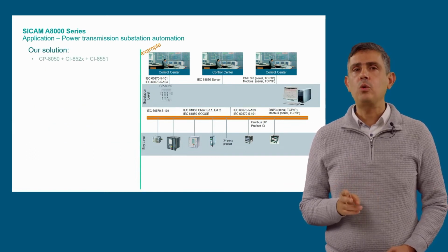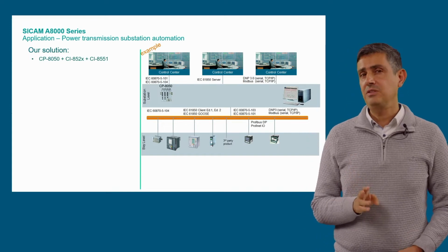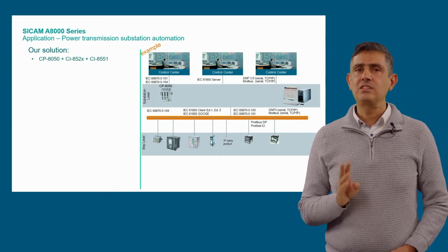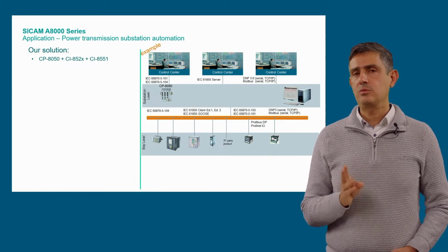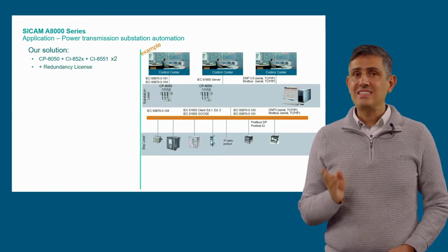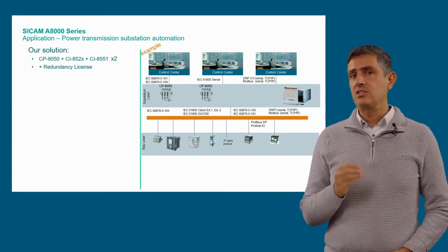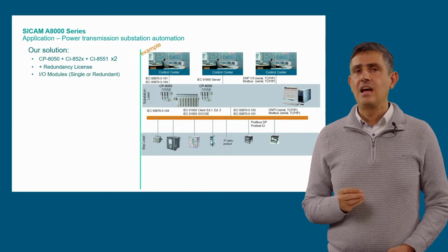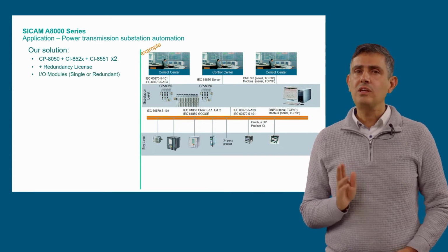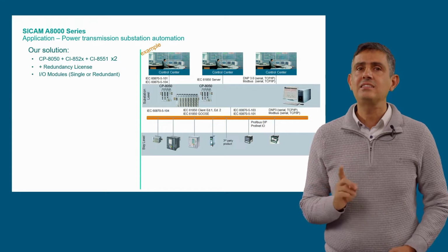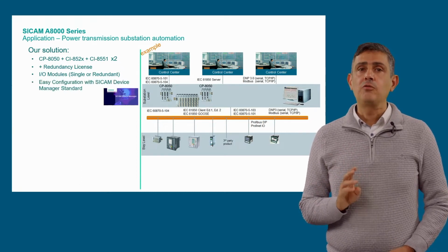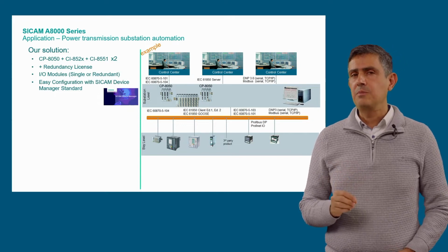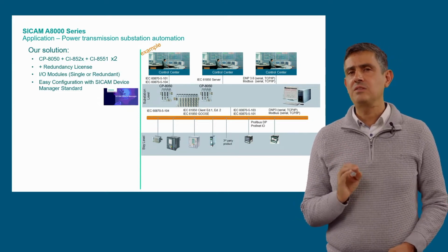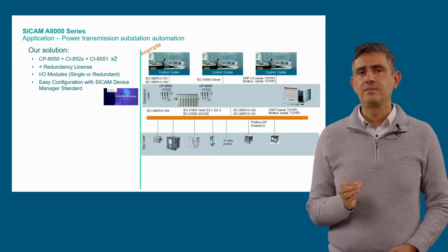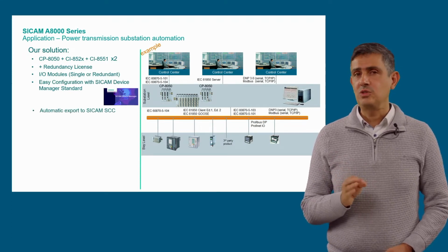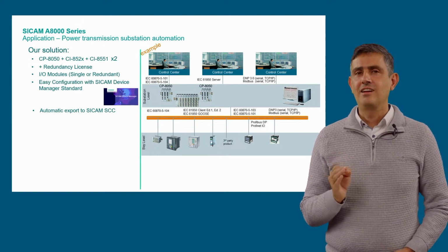Our solution for this application would normally include our powerful CP8050 extended with additional LAN ports and with additional serial ports through extension communication interface modules. To make it redundant, a second set is normally provided, plus the required additional redundancy license. Additional single or redundant periphery can also be included to acquire signals not coming directly from IEDs in the substation. The configuration of a CP8050 for this application can be optimally created with the configuration tool SICAM Device Manager with the standard license. With this, the exporting of data to SICAM SCC can be done in the blink of an eye.